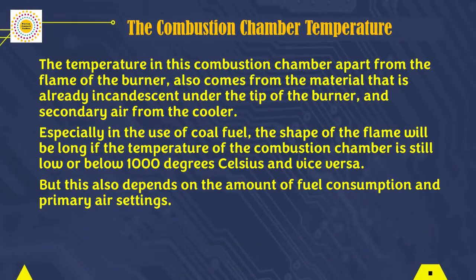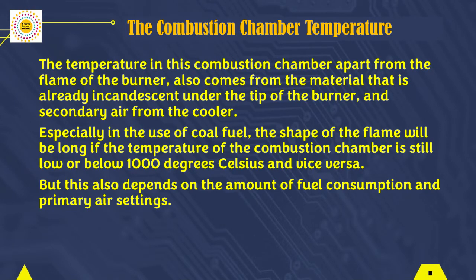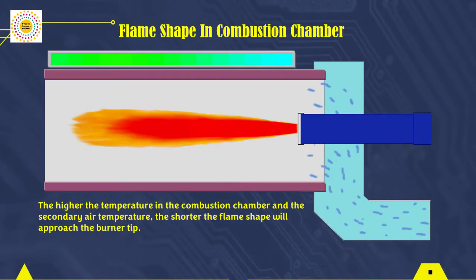Next is the combustion chamber temperature. The temperature in this combustion chamber, apart from the flame of the burner, also comes from the material that is already incandescent under the tip of the burner and secondary air from the cooler. Especially in the use of coal fuel, the shape of the flame will be long if the temperature of the combustion chamber is still low or below 1000 degrees Celsius, and vice versa. But this also depends on the amount of fuel consumption and primary air settings. The higher the temperature in the combustion chamber and the secondary air temperature, the shorter the flame shape will approach the burner tip.